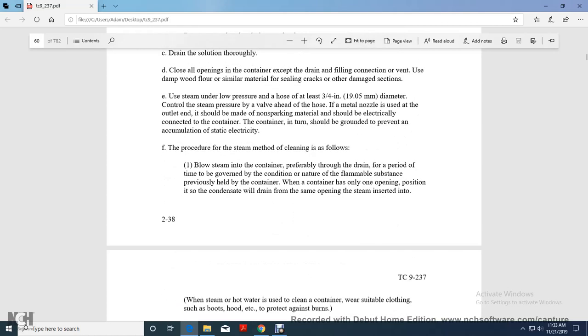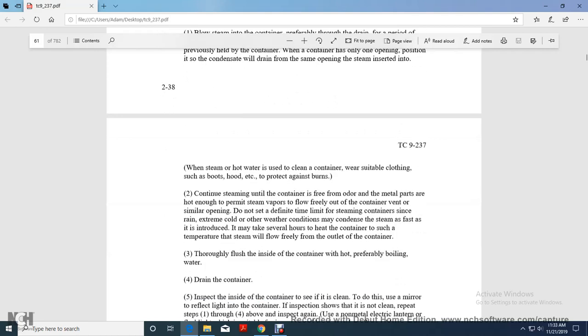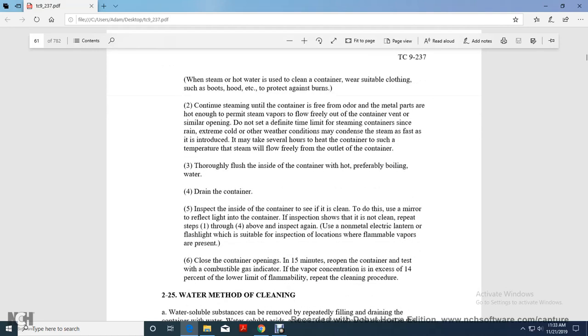The procedure for the steaming method of cleaning is as follows. Blow steam through the container, preferably through the drain, for a period of time governed by the condition and the nature of the flammable substance previously held in the container. If the container has only one opening, position the drain so that the same opening is used for the steam inserted into it. When steam or hot water is used to clean the container, wear suitable clothing, boots, and gloves to protect against burns. Continue steaming until the container is free of odor and metal parts are hot enough to permit steam vapor to flow freely out of the container vent.